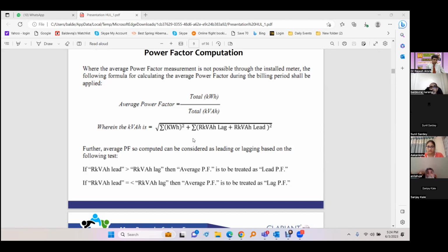So, to correct that situation, they made a deviation in the tariff structure, saying that the leading power factor also will be taken into account while calculating your kVAH. When the leading power factor is taken, they continuously record RKVAH lag and RKVAH lead, and they use this formula to find out the actual kVAH requirement. So when you are going to leading, you don't get the full advantage.